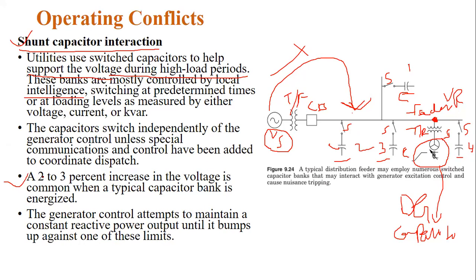Now see, a 2 to 3% increase in the load voltage is common when the capacitor bank is energized. Whenever this capacitor is switched onto the feeder, a 2 to 3% voltage variation is common. The voltage is increasing.